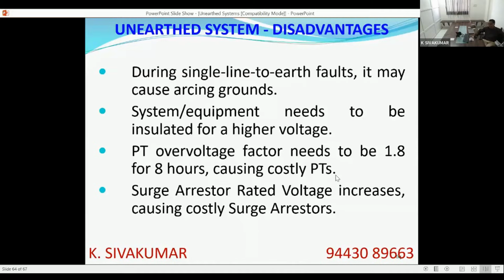Similarly, the surge arrestor rated voltage calculation depends upon something called the ground fault factor. The ground fault factor is 0.8 for solidly grounded systems, and it will vary from 0.8 up to 1.732 for unearthed systems. So definitely for an unearthed system, if you want to use a surge arrestor, you have to use a higher rated voltage arrestor, which will make the arrestor bulky and costly also. So these are some of the disadvantages of the unearthed system.